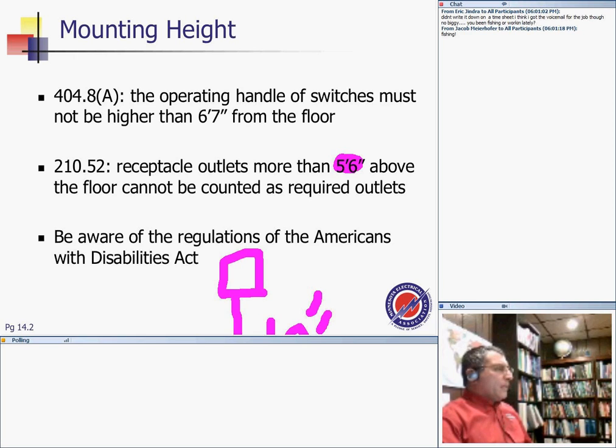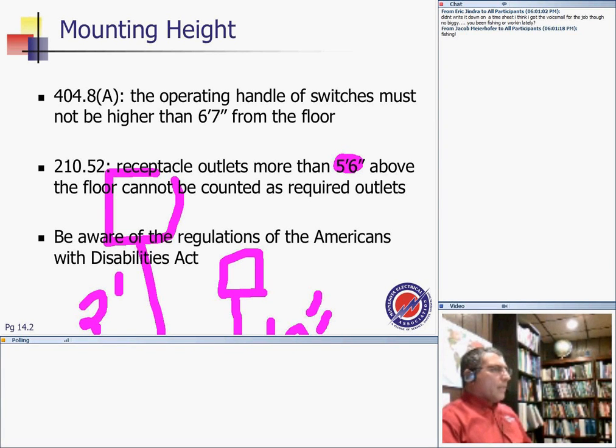Really, how about I put my receptacle here at 2 feet above the finished floor? Is there anything wrong with that? There's not any section in the code book that tells you how high you can put your receptacle. Switches, Chad. How high can I put my switch? Can I put my switch at 4 inches or 42 inches or 48 inches?